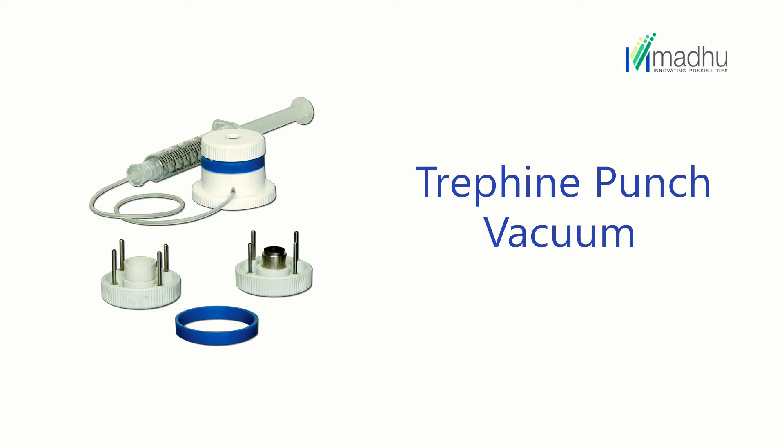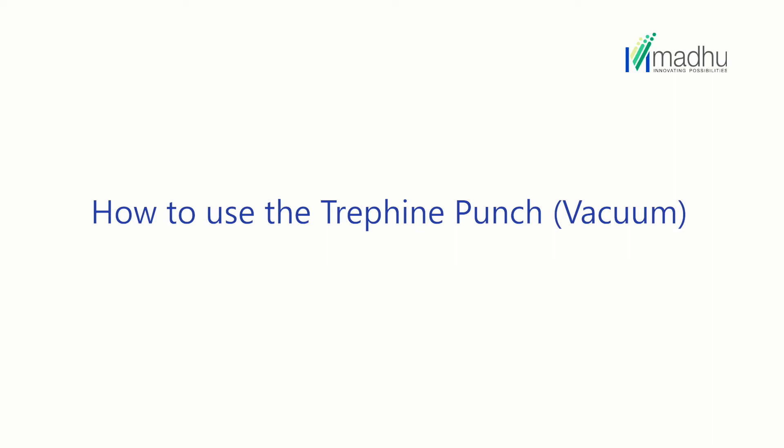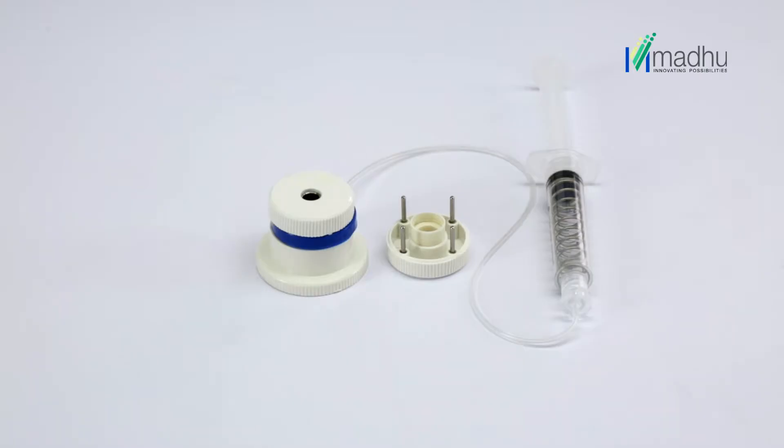The vacuum trephine punch is designed to take out a circular corneal button of predetermined diameter from the donor cornea. This device uses vacuum to hold the donor cornea in place before cutting the corneal button.